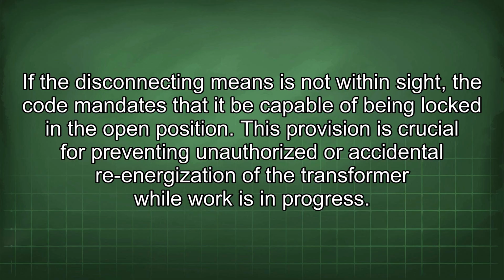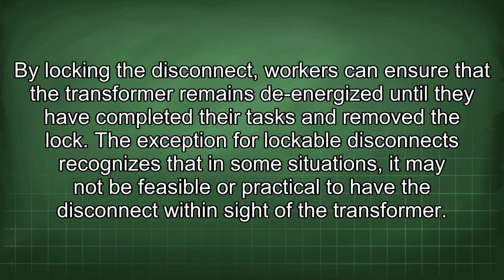If the disconnecting means is not within sight, the code mandates that it be capable of being locked in the open position. This provision is crucial for preventing unauthorized or accidental re-energization of the transformer while work is in progress. By locking the disconnect, workers can ensure that the transformer remains de-energized until they have completed their tasks and removed the lock. The exception for lockable disconnects recognizes that in some situations, it may not be feasible or practical to have the disconnect within sight of the transformer.